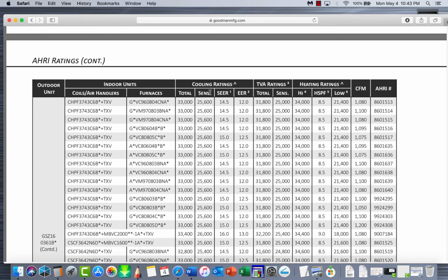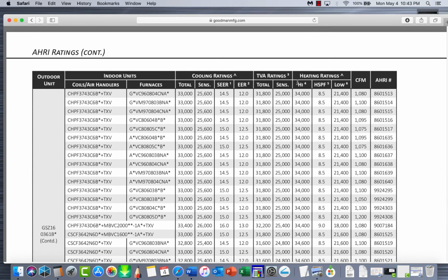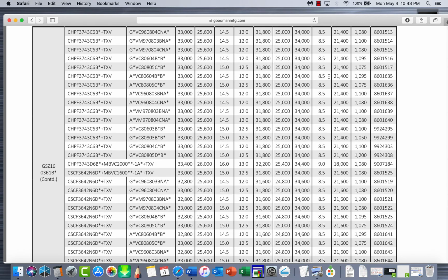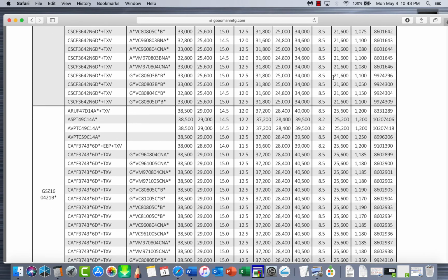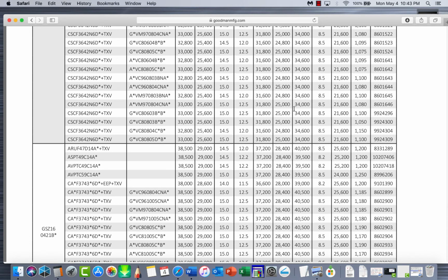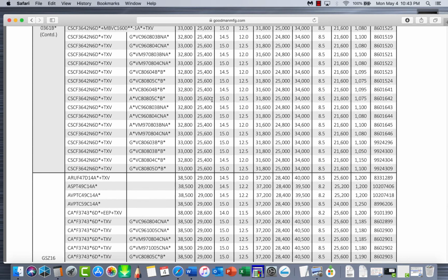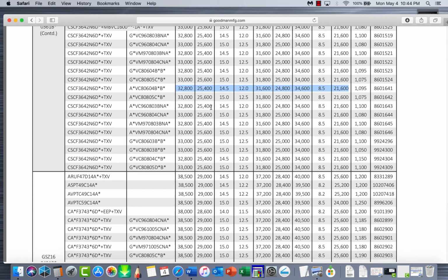But for your sensible cooling, for the heat pump itself, use the sensible. And for this one right here, we want to look at low and high. So we know 21,000 to 34,000, that would totally meet that demand on that furnace. But once again, this package over here, let's just take a look at this one right here. So 21,000, not big enough to keep our house cool in low speed. But 34,000 is, so that would work. But over here, 25,400 does not meet our sensible heating and cooling that we need. So we're going to have to move to a bigger unit.